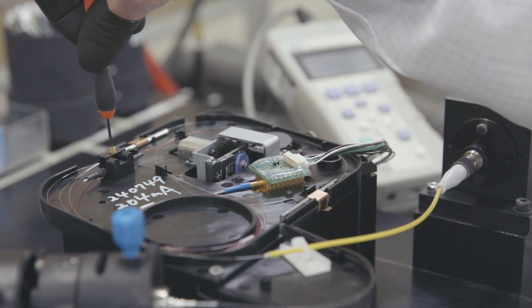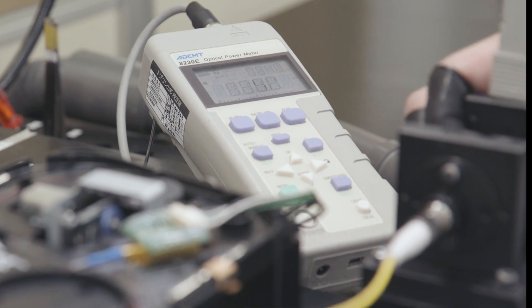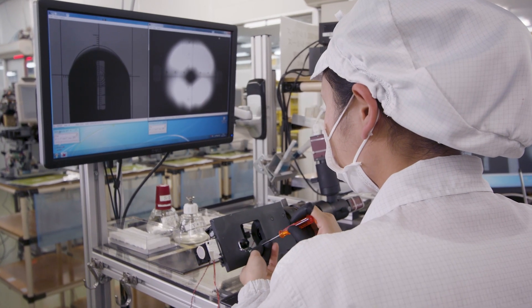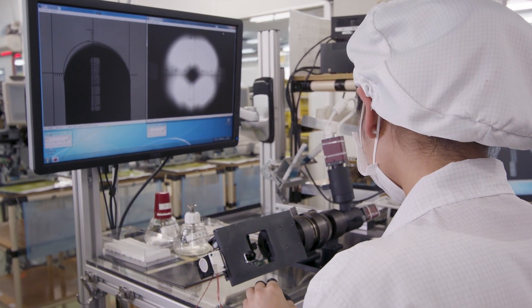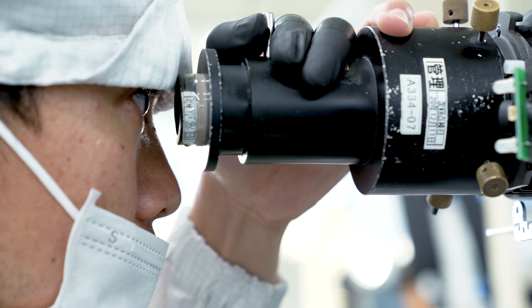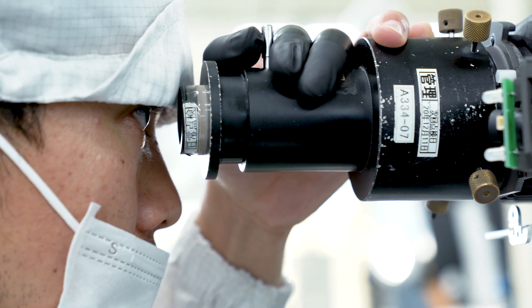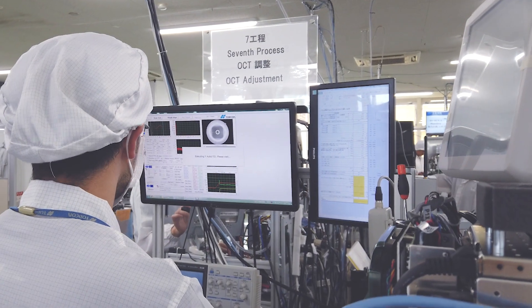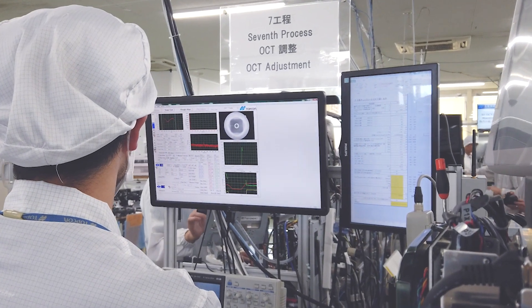The optics of an OCT are carefully placed and subtly tuned for maximum sensitivity. During each stage of manufacture, meticulous care is taken to keep the requisite balance between the camera lens, mechanical elements, and laser signals in order to perfect the tissue response within the deep layers of the retina.